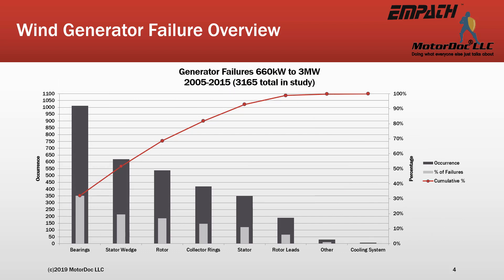In the wind turbine industry, doubly fed induction generators have specific failure modes. While bearing replacement is a larger percentage of generator issues, the total of electrical component failures is greater than bearings, which is unusual. The primary issues found in the generator tend to be stator magnetic wedges coming out or moving, and rotor wiring failures in several designs. Note that gearbox and main bearing issues can also be detected with EMPATH.